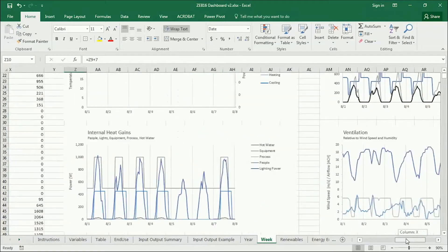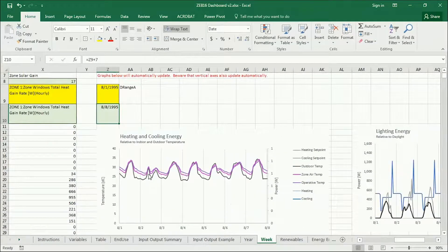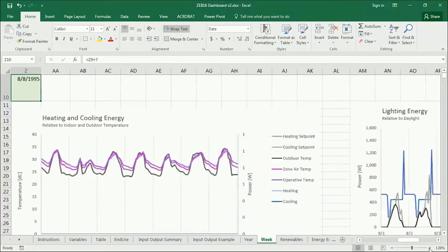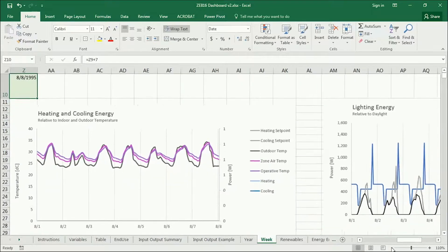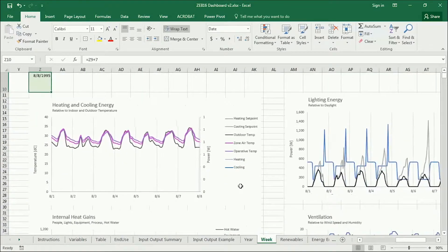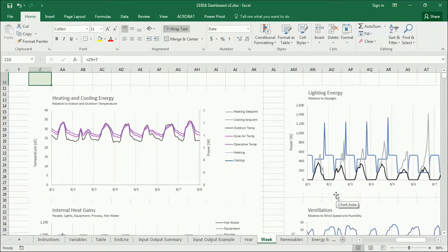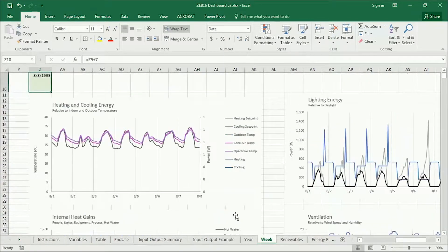If we go to August 2nd, you can see it's not as hot a day. Because the indoor temperatures are always higher than the outdoor temperature, it's always beneficial to get that ventilation in. Notice that the absolute values here — these temperatures are still quite warm, we're in the 30 degrees Celsius range — so you'd probably want cooling anyway. But this is just a window into what happens in this completely naturally ventilated building.